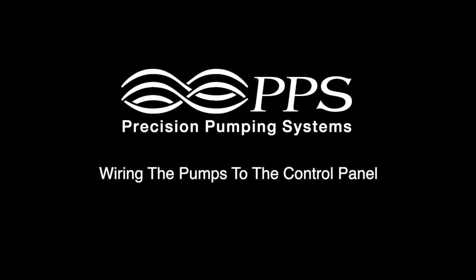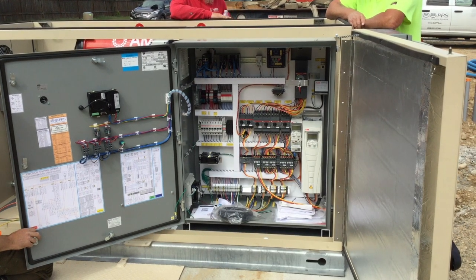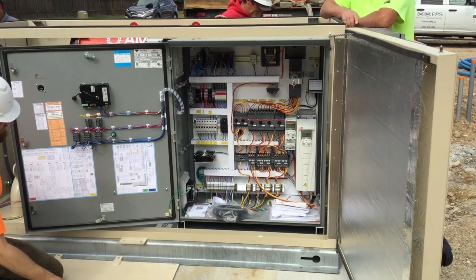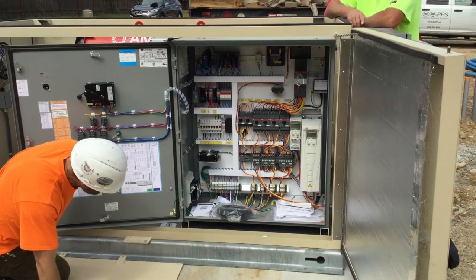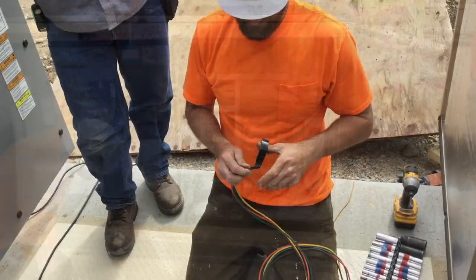The final step is to connect all pump motor lead wiring to the control panel. Open the panel and identify the correct inbound connection for each pump per the schematic located on the panel door.